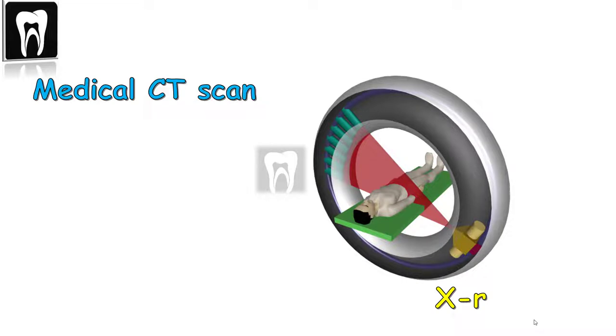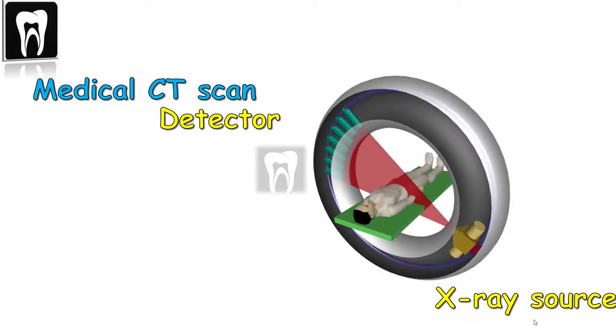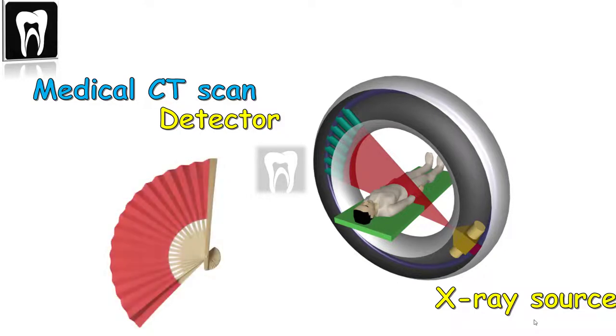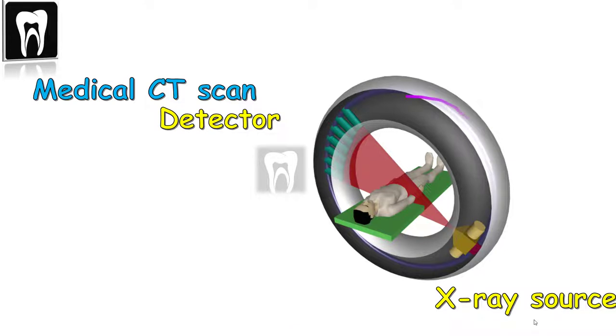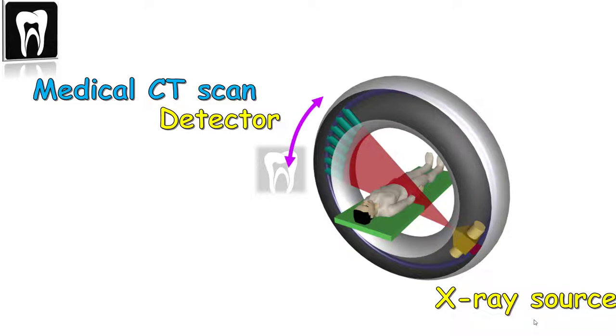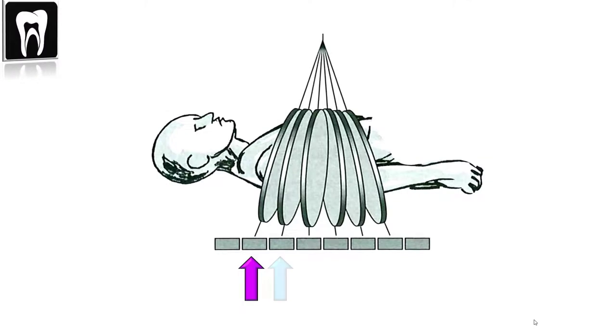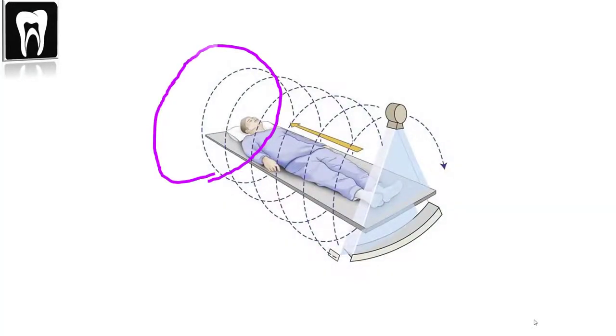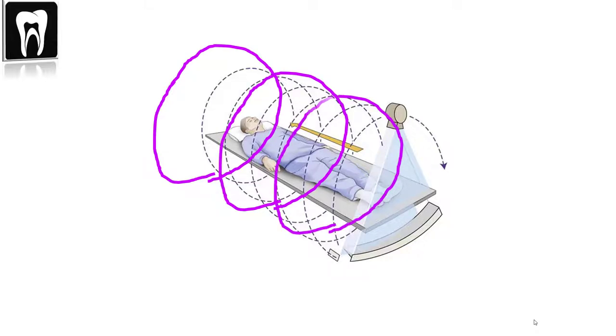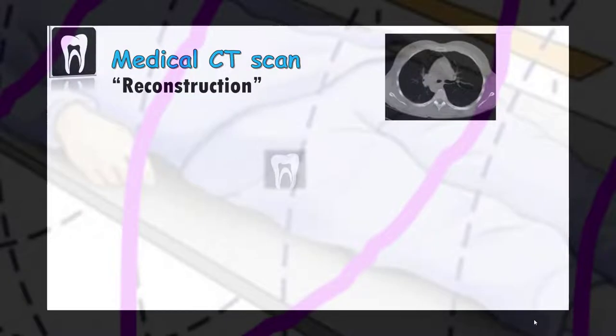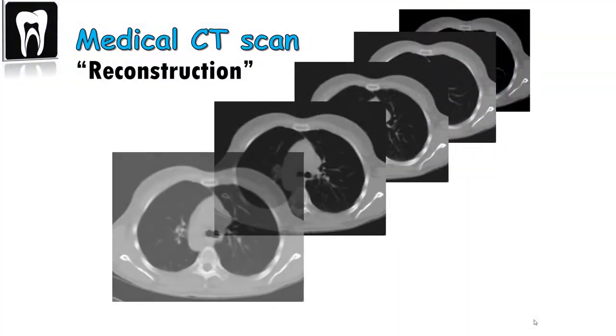Let's see how a CT scan machine works. The device uses an x-ray source and detector to capture multiple images from different angles. The shape of the x-ray beam looks like a fan that rotates, with a thin arc-shaped detector that captures limited-thickness slices. The bed the patient lies on moves inside the machine, and every time the x-ray and detector go around the patient, we get one slice image. Multiple rotations are performed, producing a single axial slice image per scan, which are then reconstructed into a 3D image.